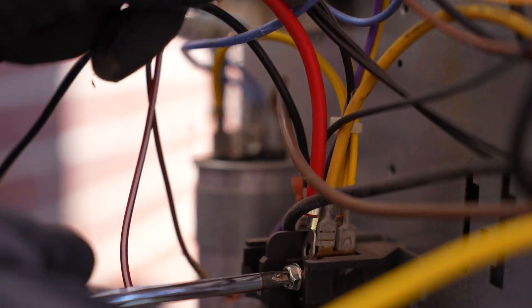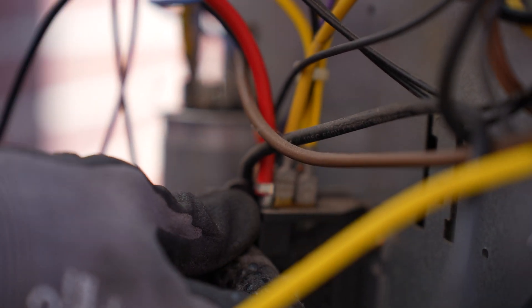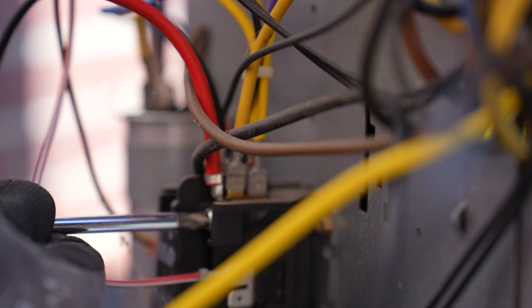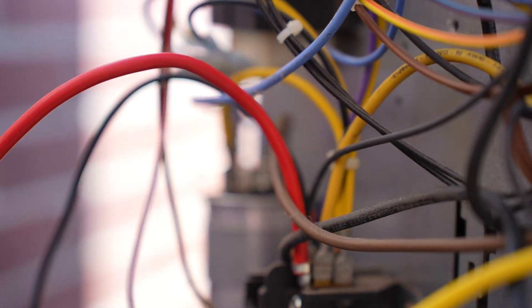The black wire supplied goes from terminal C on the Soft Starter — fits very nicely — down to the Faston connection on T1 of the contactor. A little wiggle seat, and there it is. Always give it a tug test and a visual inspection. Looks good. Step three: 10-gauge wire from the Soft Starter as defined, down to T2 on the contactor. Beautiful. You don't want to over-torque and don't want to under-torque. Nice fit, always a tug test. Well done.